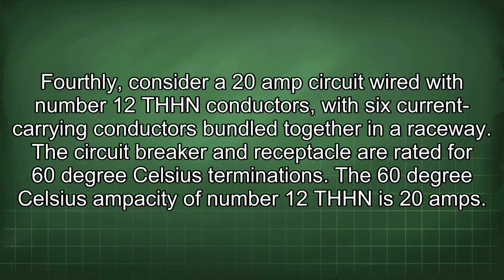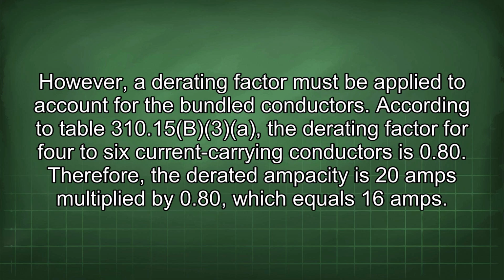Fourthly, consider a 20 amp circuit wired with number 12 THHN conductors, with 6 current carrying conductors bundled together in a raceway. The circuit breaker and receptacle are rated for 60 degrees Celsius terminations. The 60 degrees Celsius ampacity of number 12 THHN is 20 amps. However, a derating factor must be applied to account for the bundled conductors.